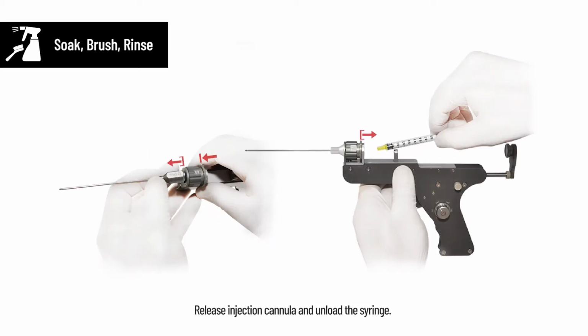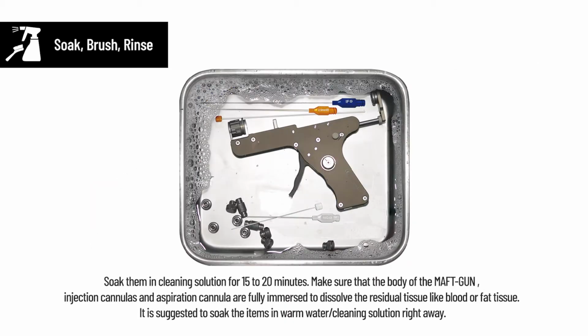Release injection cannula and unload the syringe. Soak them in cleaning solution for 15 to 20 minutes. Make sure that the body of the MAFT gun, injection cannulas and aspiration cannula are fully immersed to dissolve the residual tissue like blood or fat tissue. It is suggested to soak the items in warm water/cleaning solution right away.